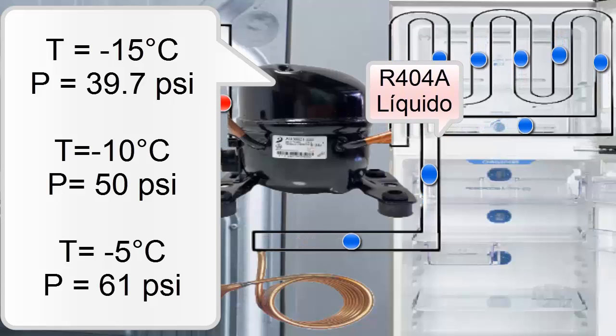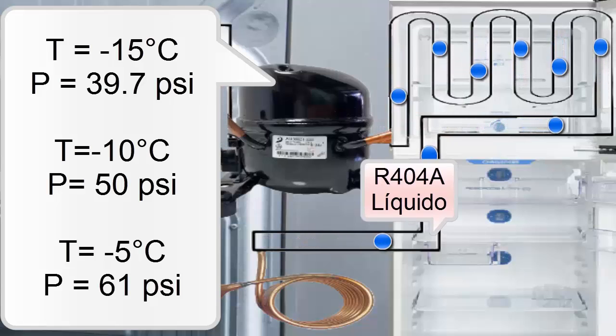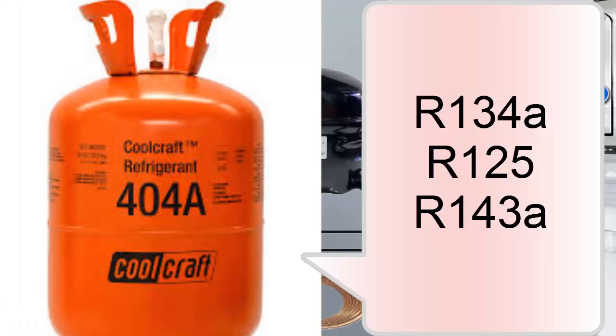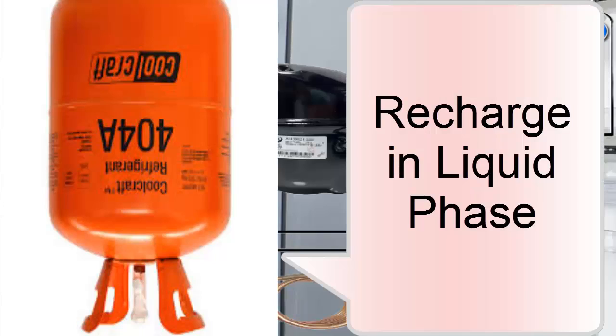The R404A refrigerant presents excellent efficiency. It is internally composed of three gases: R134A, R125, and R143A. Since it is internally composed of various gases, the R404A must be introduced or recharged into the equipment always in a liquid phase.